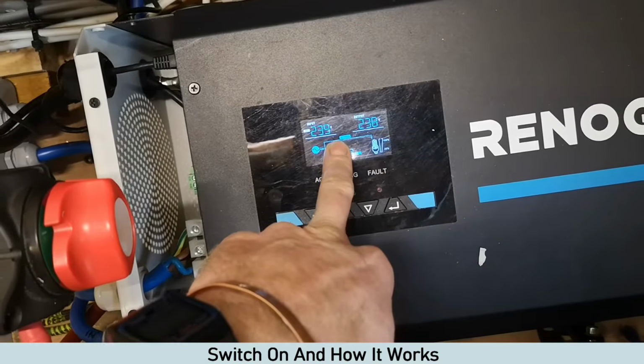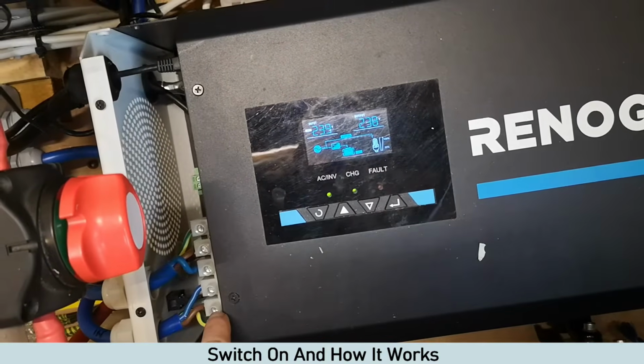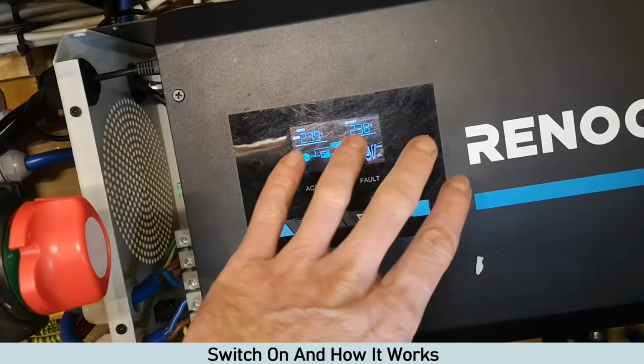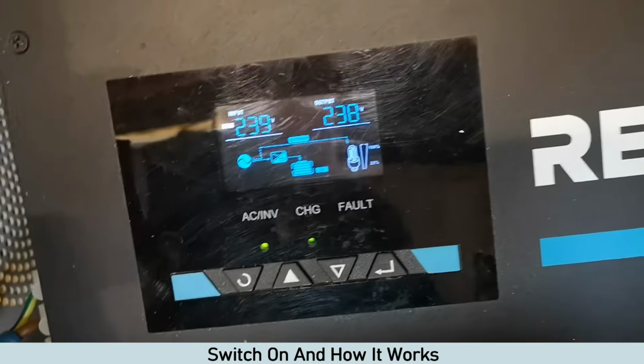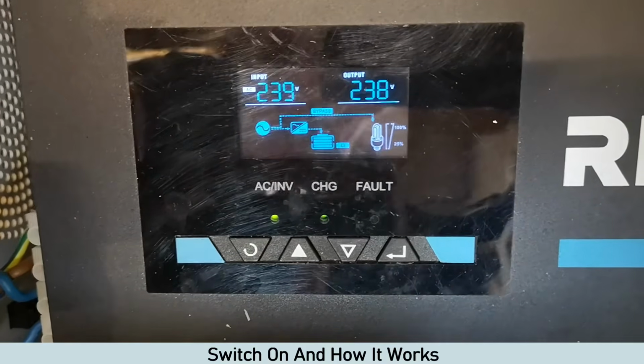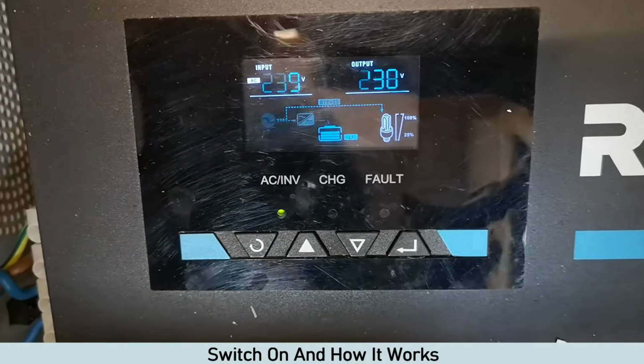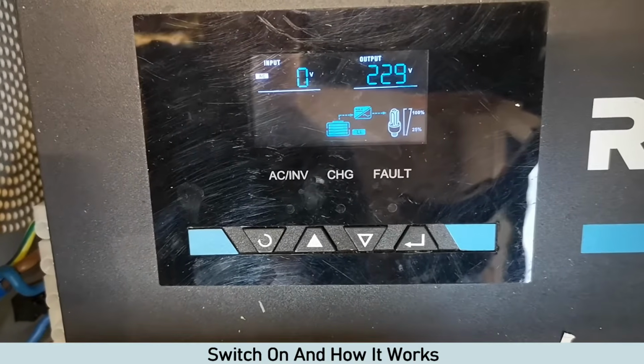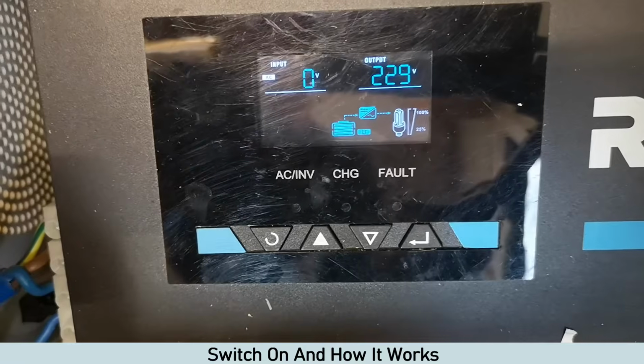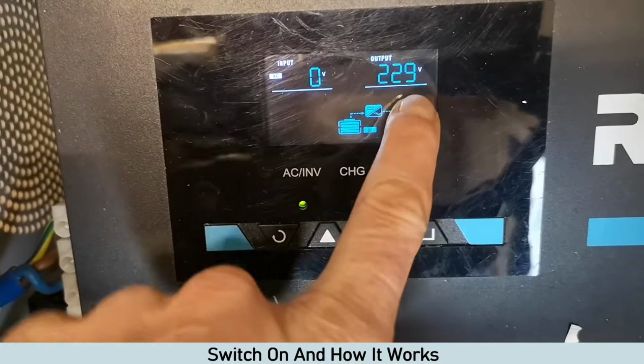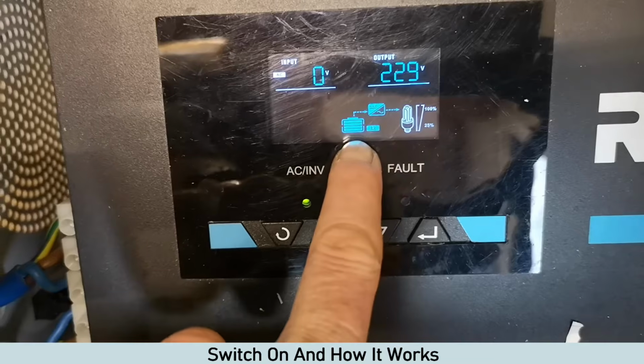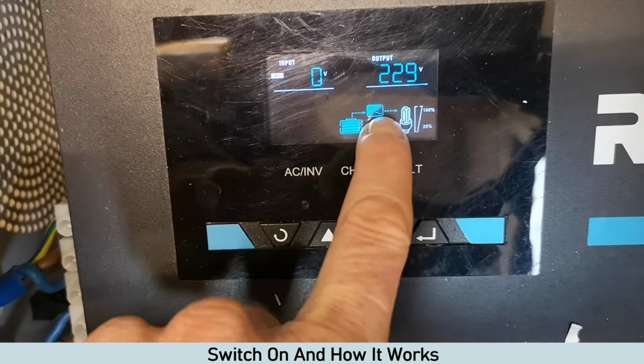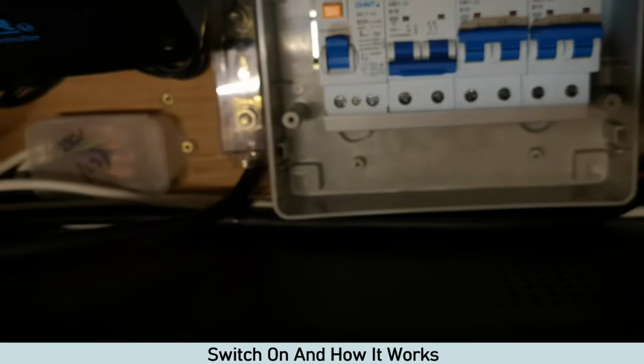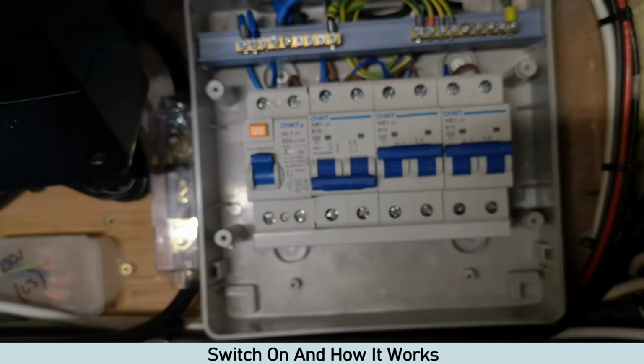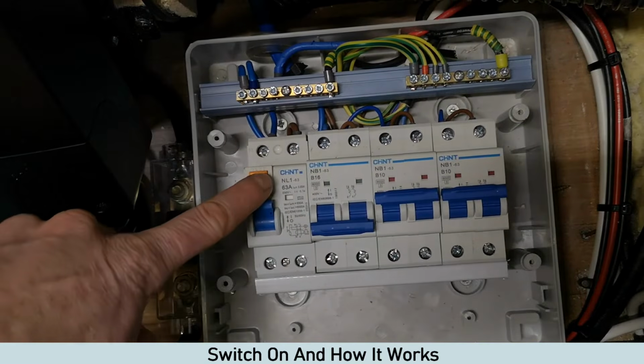And then what's going to happen is, because this has got that auto relay switch inside, when it senses there's no power coming in, it immediately switches to inverter. So what you'll see is the bypass disappear and switch to inverter. So I'll just turn the RCD off. There we go, and it's pretty much immediate. So now we've got no power coming in. Obviously input is 0, but the output is 229 volts. So obviously we're feeding off the battery, pulling 12 volts off the battery, and then putting power onto DB2 again.